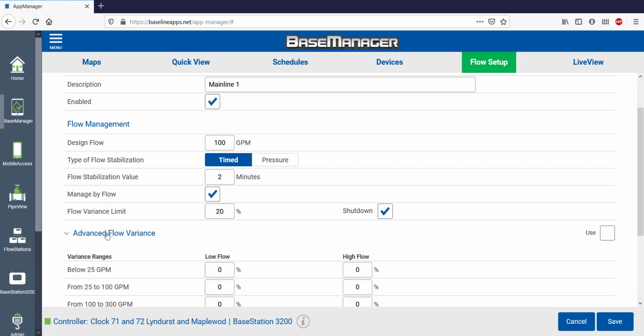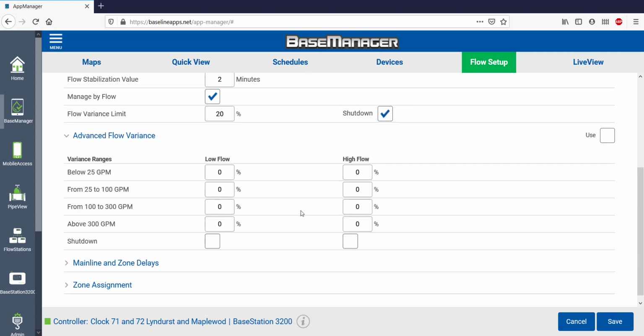A useful setting is Advanced Flow Variance. If I select the box Use on the right side, it will ignore the above flow variance settings. I'll get the option of adding a range of flows based on my expected flow. I've decided for flows 300 GPM and above, I'll only tolerate a 5% variance. For flows between 100 and 300 GPM, I'll tolerate a 10% variance. And then all the way down to flows 25 GPM or less, I'll tolerate a full 20% variance.